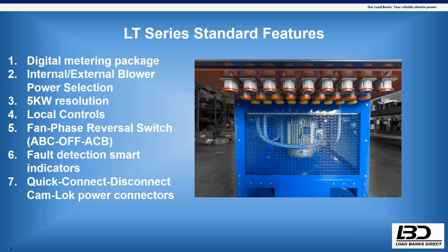All the units offer a fan phase reversal switch. So say someone's not paying attention, or you hook up all your Camlocks and don't have your phasing right, there's a switch so you can avoid disconnecting and rewiring the whole thing. It rearranges the phasing so your blowers are blowing up through the resistors instead of down, switching the rotation of the blower. That's a nice, time-saving feature if the connections are overlooked or done backwards. It's standard on all of our trailer mounted gear.